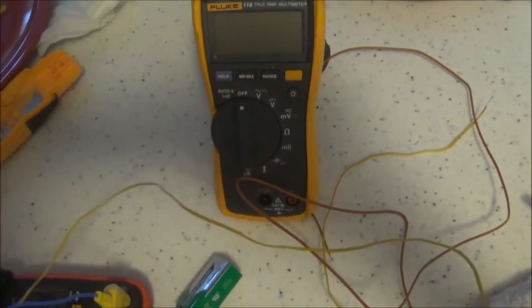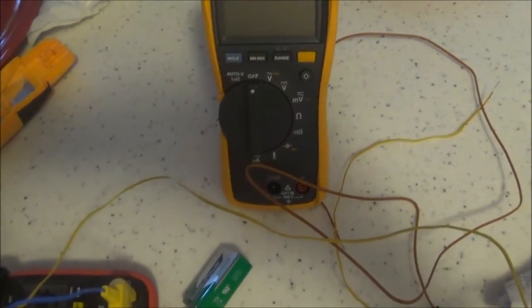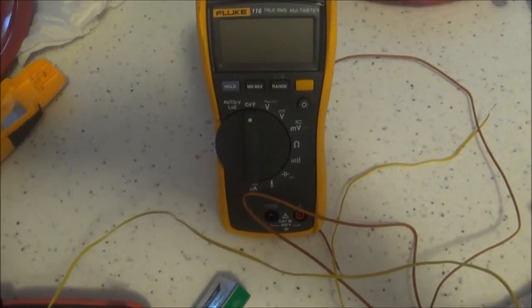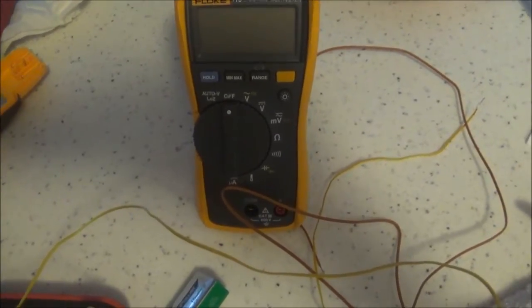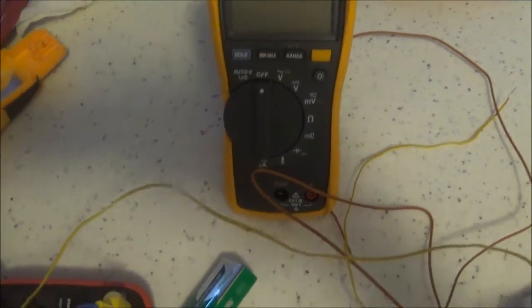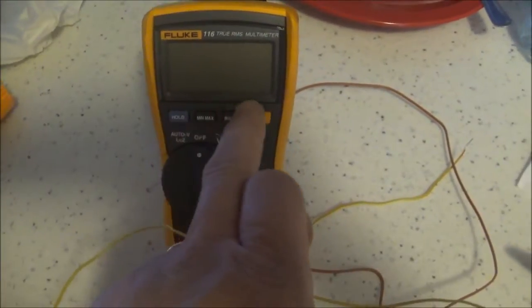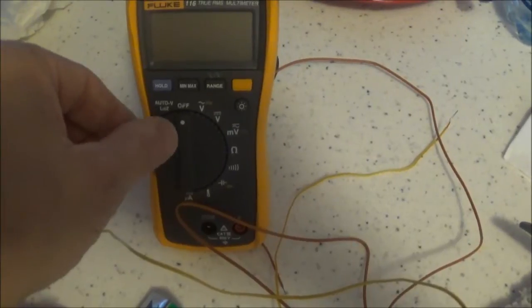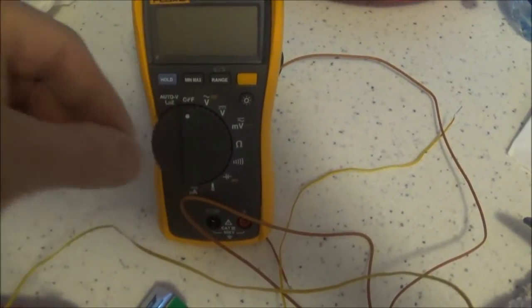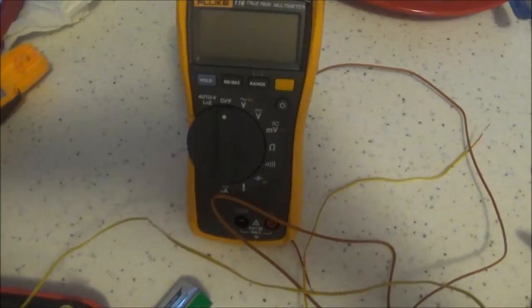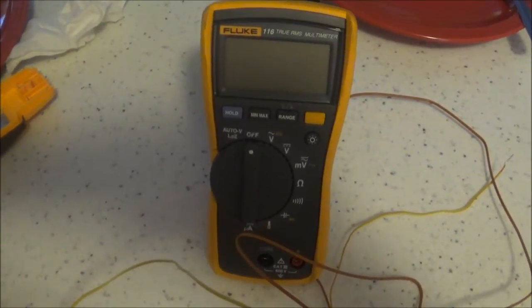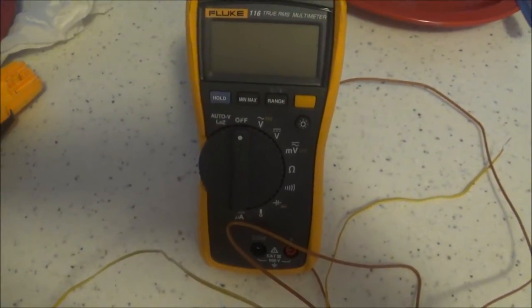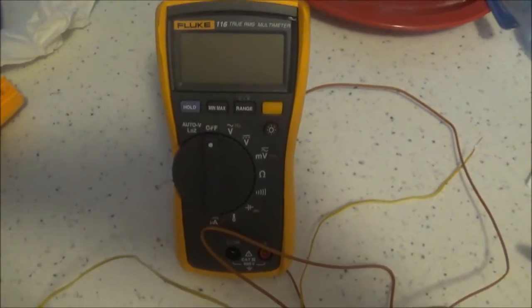This one actually, the Fluke itself reads kind of low, it reads like 31 and a half in the ice bath with its own leads. And there is a calibration procedure that I downloaded for it, and it's really in depth. It involves using these buttons to enter numbers and passwords, and you've got to turn it off, hold, turn it to a certain setting to put it in calibration mode. It's a real drawn out process, something that if you really took your time and had all the step by steps you could probably do it, but it's one of those things I'm not willing to do over half a degree.